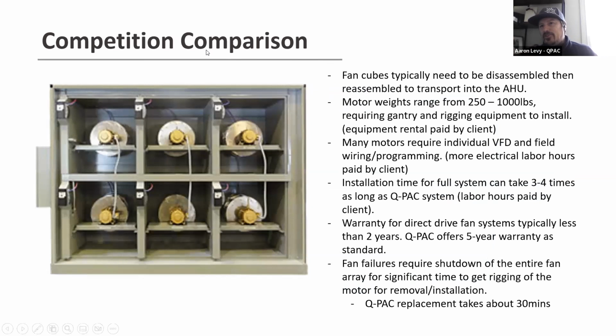So we talk about our competition and what you may face out in the field or what we may be competing against directly. These are kind of the systems that you would see, where each fan will have its own drive. What I talk about with customers, end users, even mechanical contractors, is that this system that we're competing against has motors that can weigh anywhere from 200 to 1,000 pounds. You're going to need gantry systems. You're going to need rigging equipment.